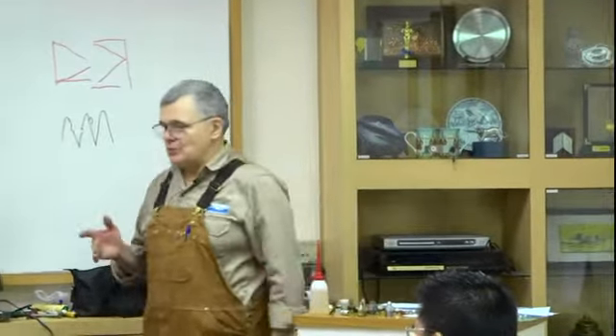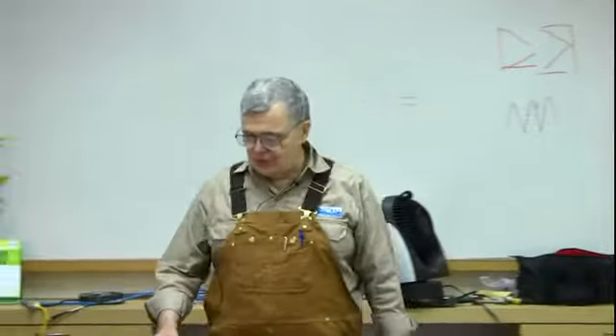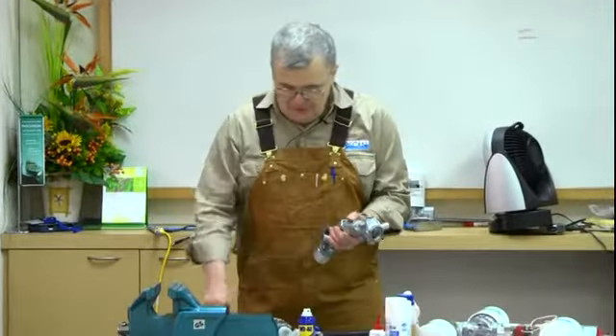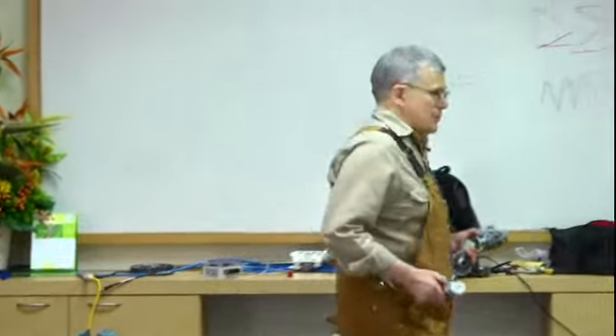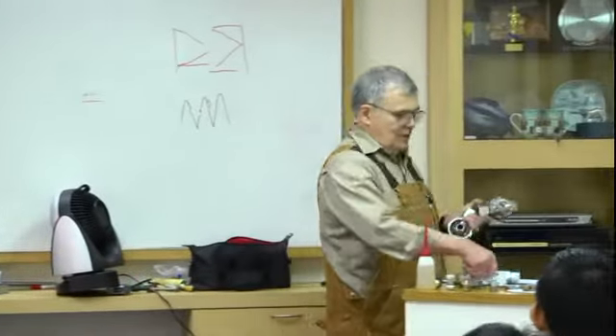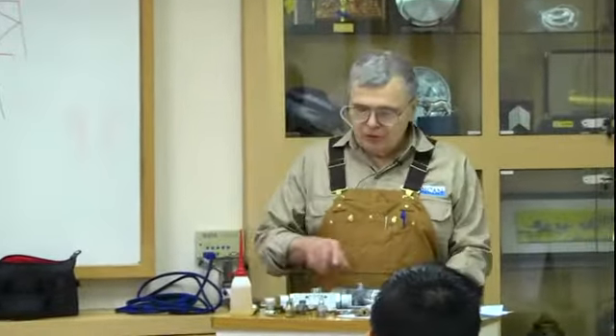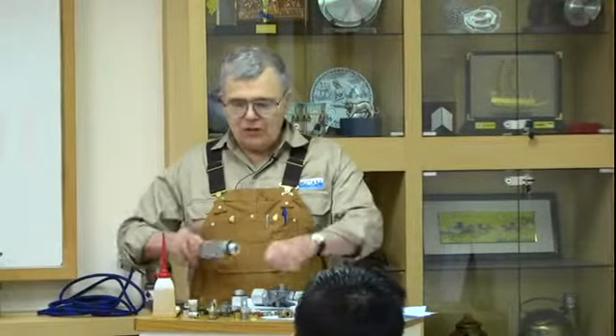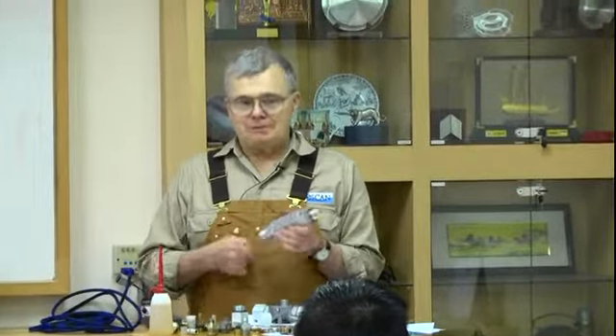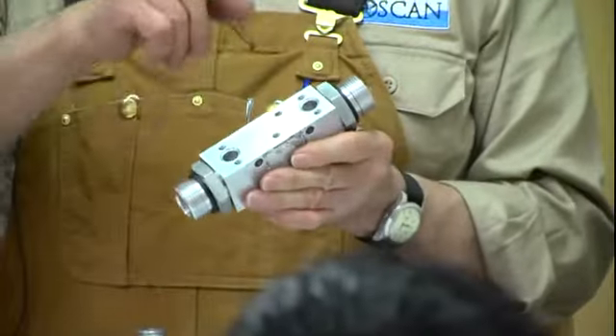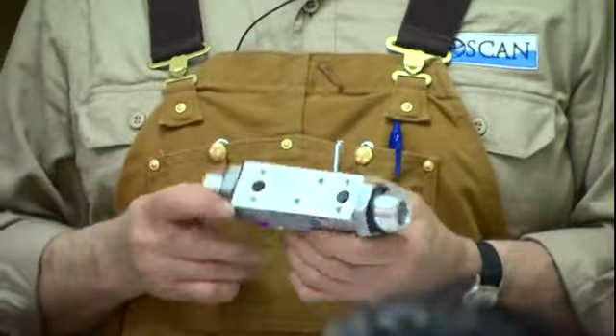Okay. Let's move on to the sensor assemblies. These are the parts of one of our high flow sensors. I don't have the sensor that's bolted to it. This is called the proportional bypass block. The majority of the fuel goes through the block. Only some of the fuel goes through the sensor.